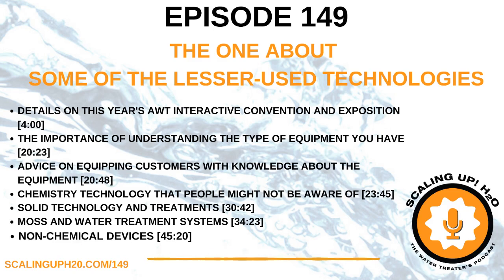And whenever it absorbs those cations, it releases a hydrogen ion. So if you add hydrogen to water, what happens? Your alkalinity is going to come down and your pH is going to come down. Well, if you're lowering your hardness levels, your alkalinity levels, and your pH, you're going to see an LSI reduction or an RSI reduction. So you're making the water a little bit more aggressive to those minerals.